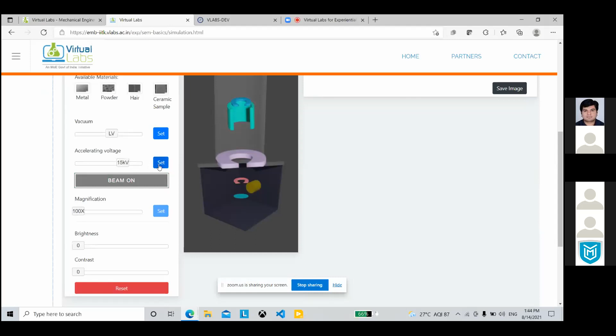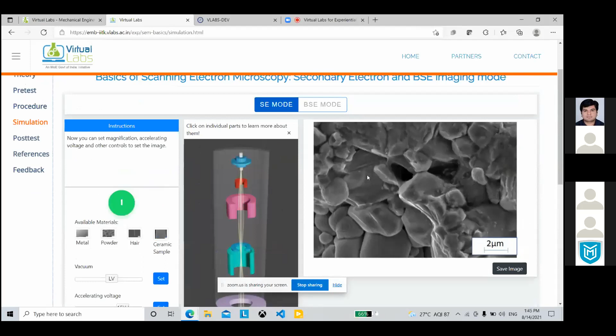I can see a small animation of how the electron beam will act, and I will get the output. This is the output that I will get from a scanning electron microscope if I keep a ceramic material under low vacuum at 15 kilovolt accelerating voltage. I can save this image for future references on my desktop. I can change the magnification of the image. I can also change the brightness and contrast. If I change the brightness now, you can see how the brightness changes here.